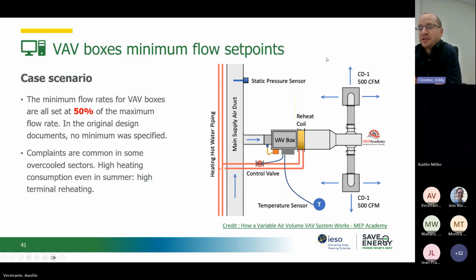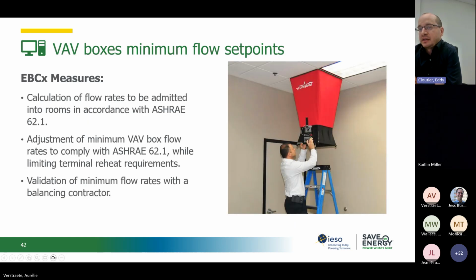Complaints were really common in that case because some sectors were overcooled, of course. And in terms of energy efficiency, it means a lot of heating consumption that is not really needed. So what could be done in that case, what would be the EBCX measure, would be to calculate the minimum airflow required for ASHRAE 62 to make sure that the minimum would be set at this set point. And it could be useful to validate the airflow with a balancing contractor in that case.